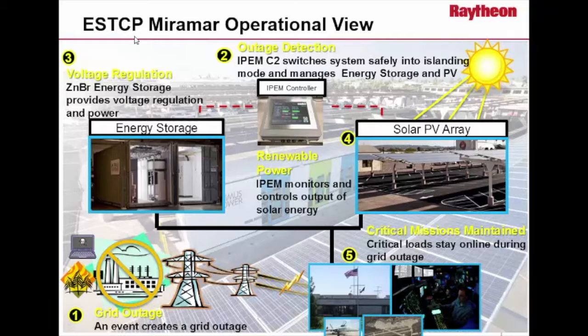Our main use case was maximizing the amount of PV penetration to keep the battery demand as low as possible, and thus extend our islanding time. The idea is to keep the critical load in the building on. There's also a follow-on to this project where we integrated HVAC load shedding, so we could reduce the HVAC demand on the building, which was by far the highest consumer of power.